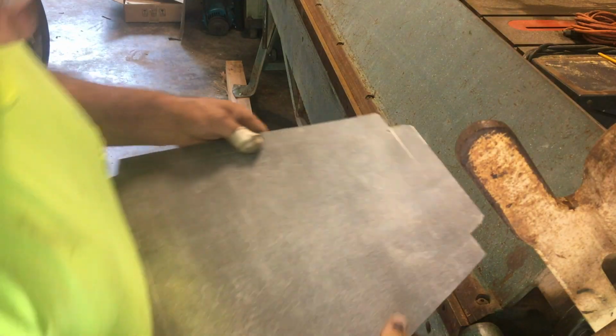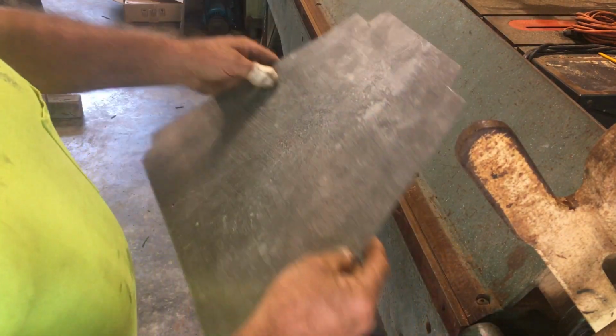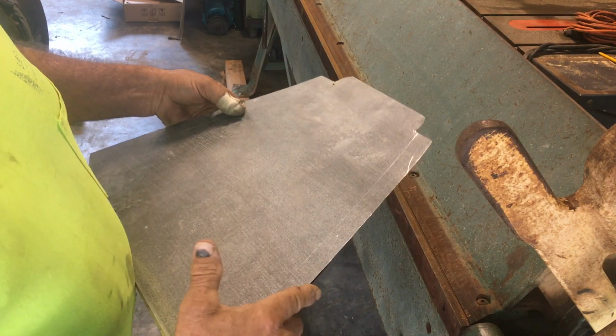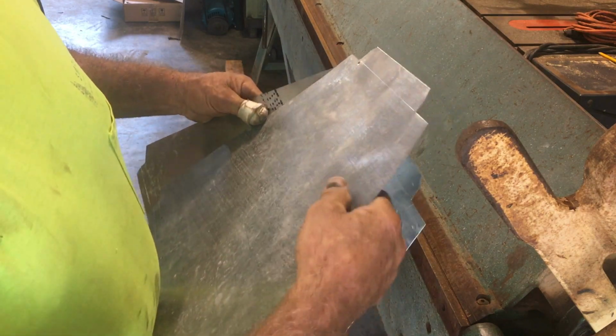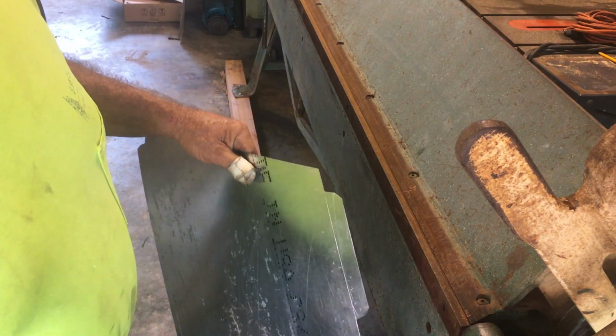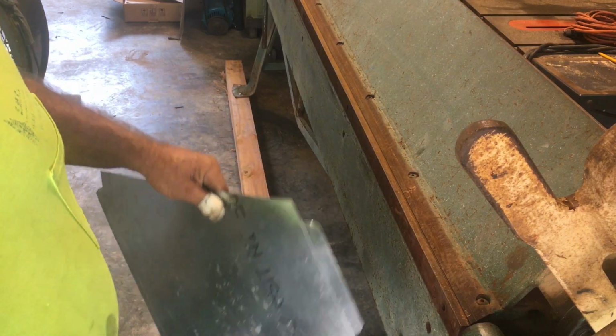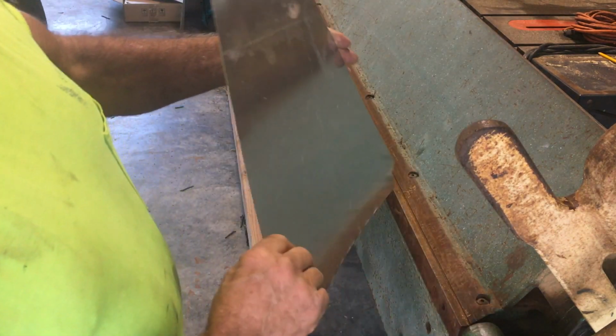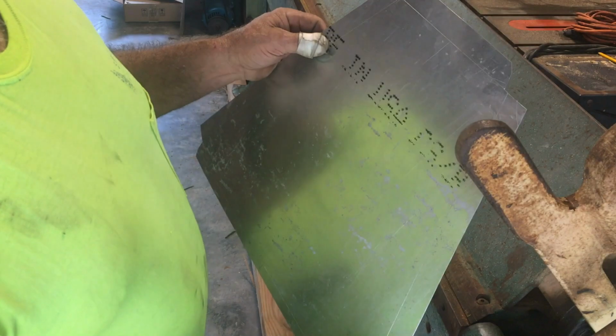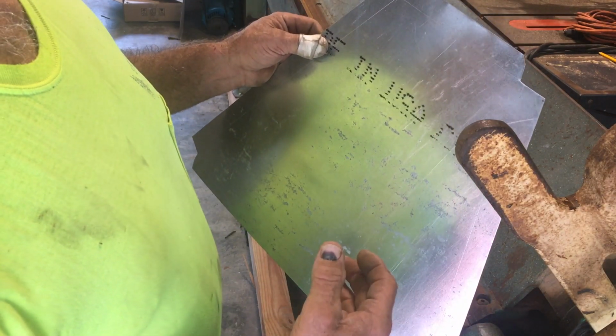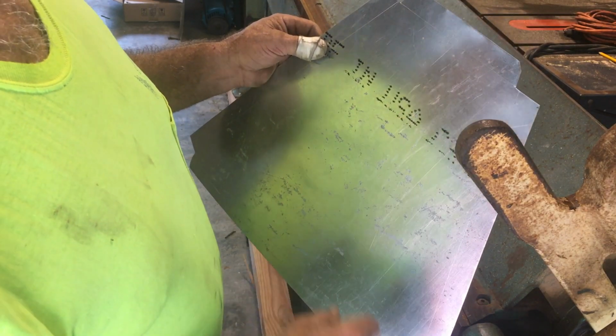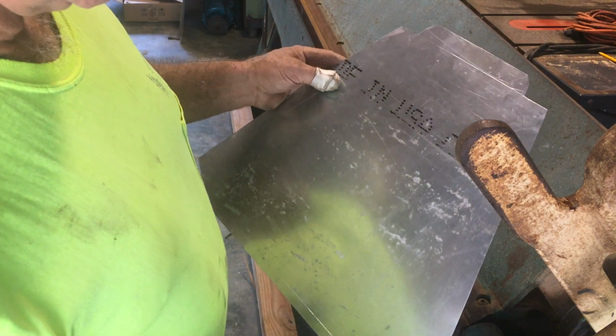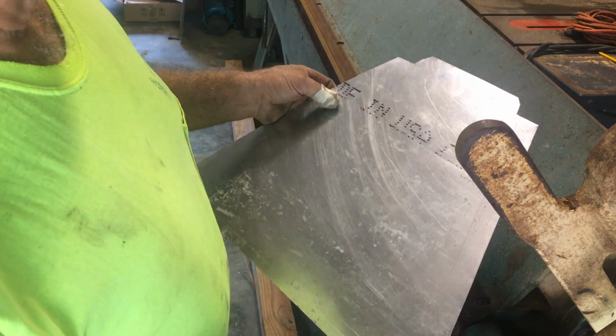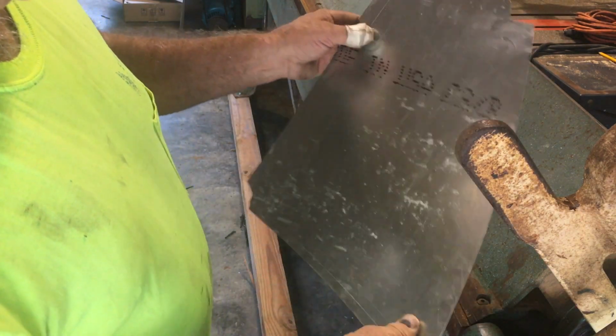Now what I like to do on these, since this is light gauge metal - well it's 26 gauge. A lot of duct in residential places is 28 gauge, but this is 26 gauge. It's heavy enough, but if there's any amount of duct static pressure - that's the amount of pressure your blower is exerting on the insides of the duct to force air out of the register - if there's any pressure in the duct at all, your duct is going to oil can.